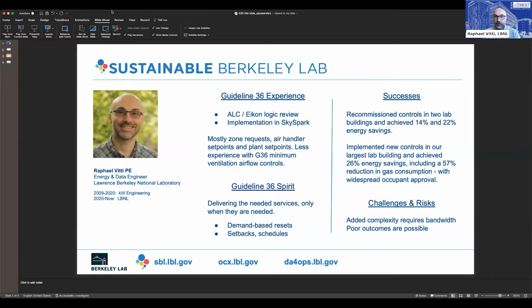We did a lot of work to support that: recommissioning the zones, fixing a lot of leaky reheat valves, broken dampers, and whatnot. We had really good success in that building, achieving 26% overall energy savings, including a 57% natural gas consumption reduction. So that's my main experience with Guideline 36.